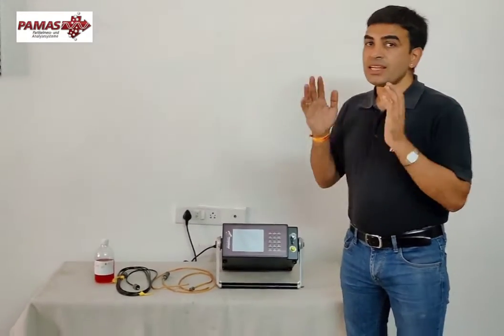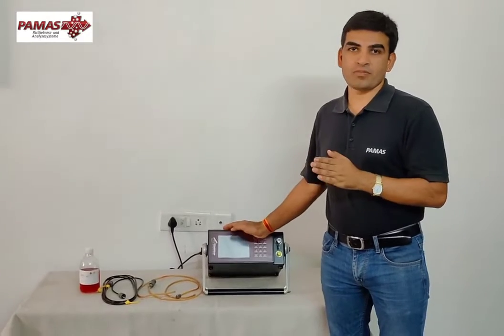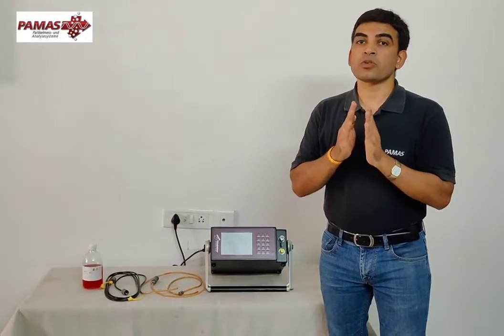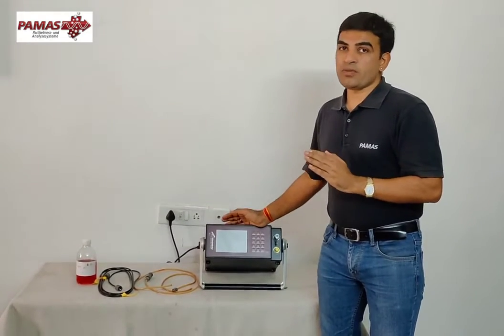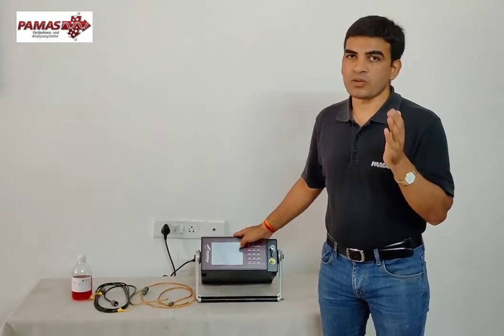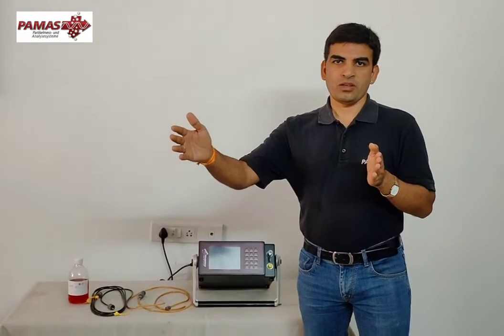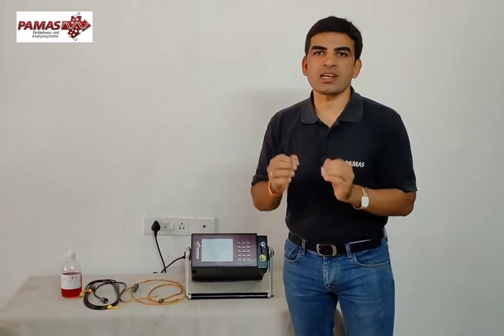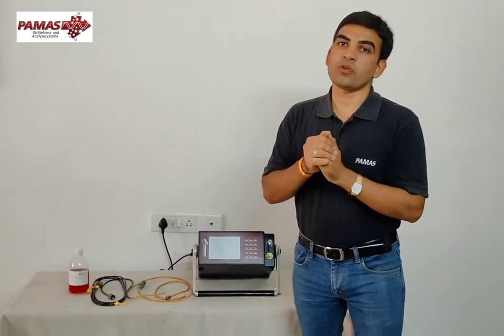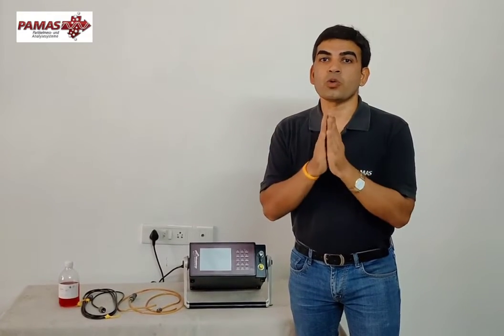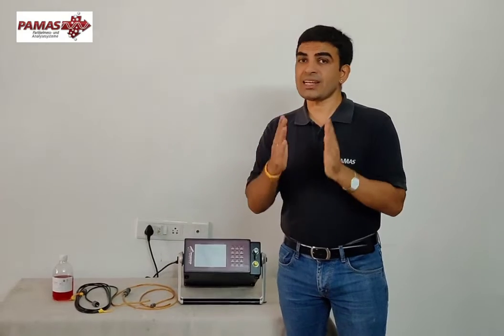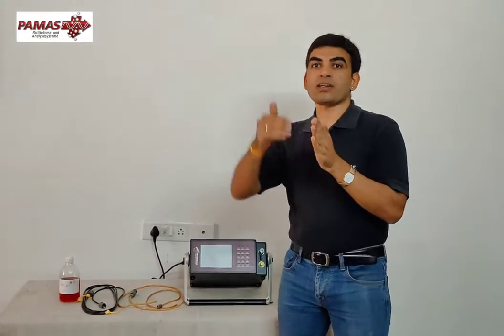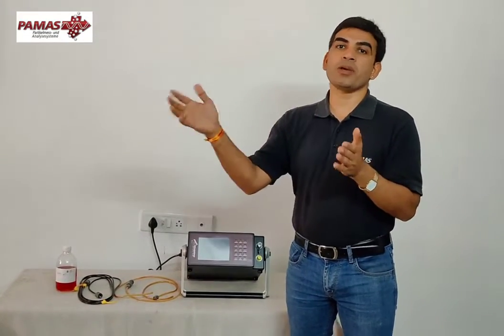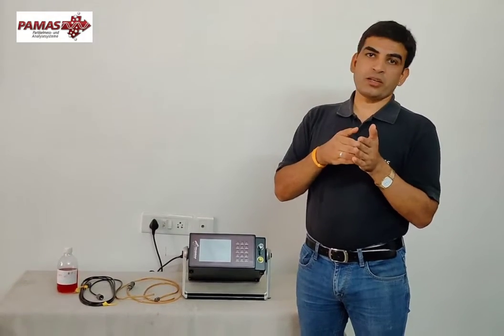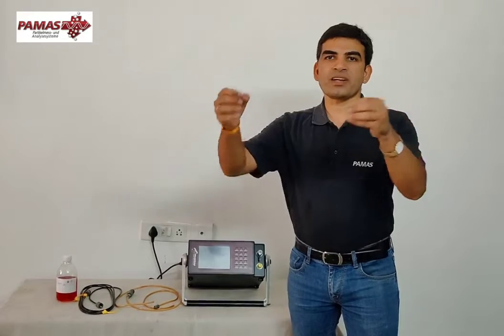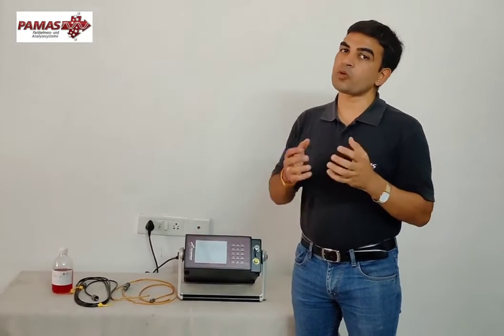This is highly accurate. It can have both calibrations at the same time, ISO 11171 as well as ISO 4402 calibration. If you have only one calibration, for example 11171, you won't get the NAS value. To get the NAS value, you must have the instrument calibrated as per ISO 4402, because both calibrations are totally different. One single calibration cannot give you the data for another standard. If you have ISO 11171, you won't be able to get data for ISO 4402 calibration, which means you won't get the NAS value. You must have two separate calibrations, and our instrument has the capability of having both of them.